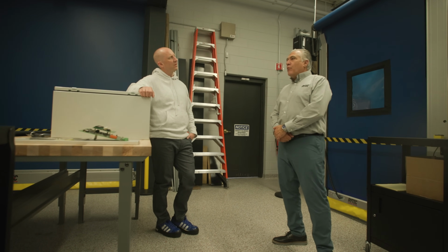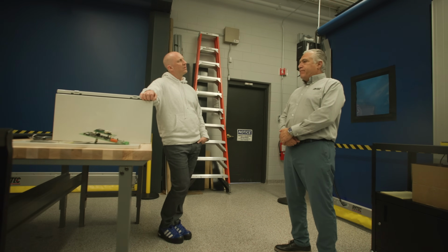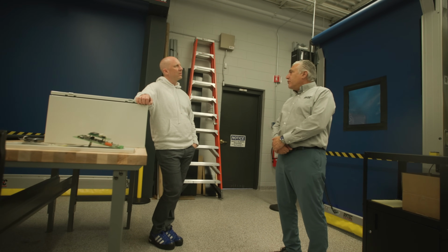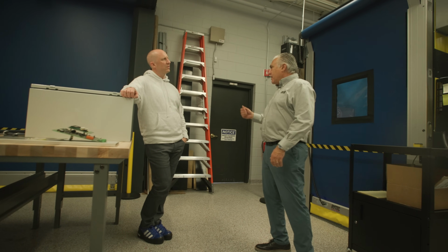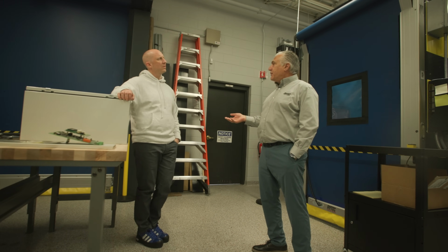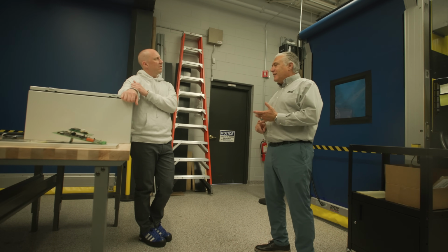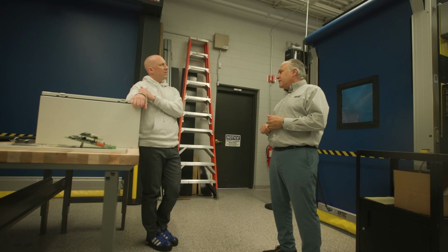So our standard is three-phase, but we do have hundreds and hundreds of doors in 230-volt single phase, but not 110. So you can't use conventional 110 volt, but you can use 230 volt single phase. We even have some doors that are 208 volt. A lot of it depends on the size of the door and how many cycles it has.